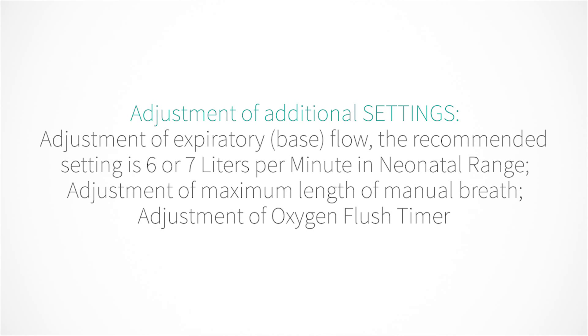Adjustment of additional settings. Adjustment of expiratory base flow — the recommended value is six or seven liters per minute in the neonatal range. Adjustment of maximal length of manual breath. Adjustment of oxygen flush timer.